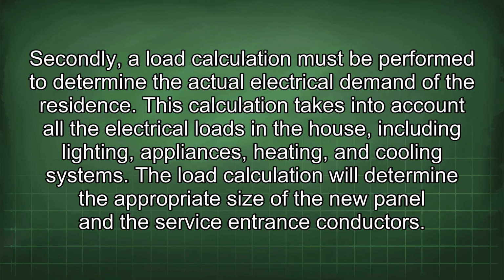Secondly, a load calculation must be performed to determine the actual electrical demand of the residence. This calculation takes into account all the electrical loads in the house, including lighting, appliances, heating, and cooling systems. The load calculation will determine the appropriate size of the new panel and the service entrance conductors.